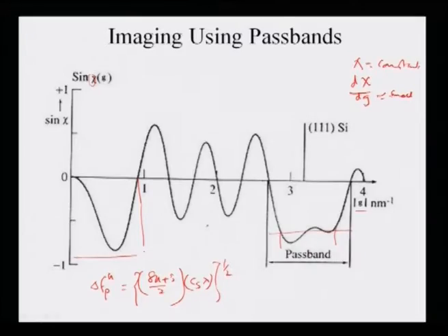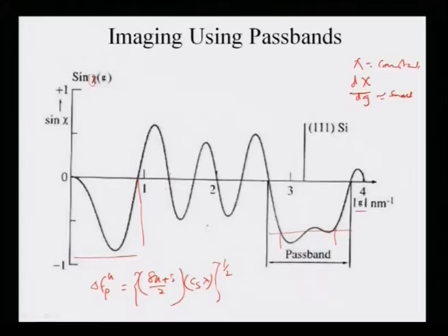The only price we pay is that now there are many extra zeros, 1, 2, 3, 4, 5, other than the first zero. Zeros correspond to no output signal, so more zeros mean less information transfer at lower spatial frequencies, and the transfer function will be heavily affected. That is the only problem, but this is used widely to select the focus in high resolution electron images in many microscopes.